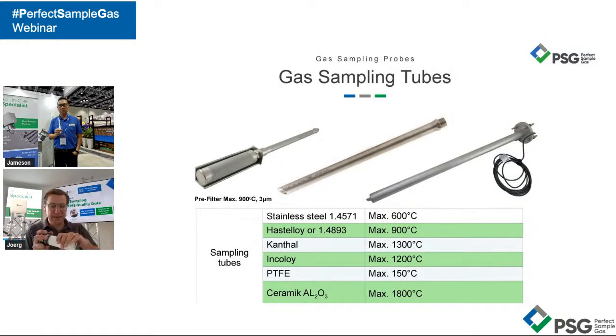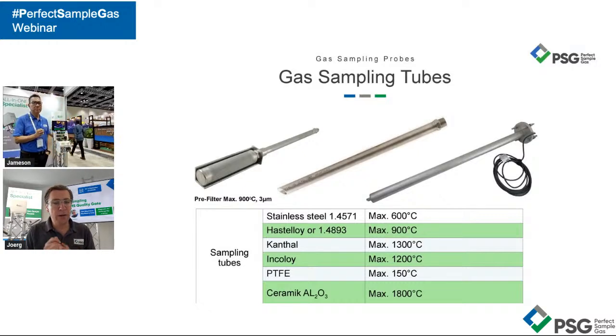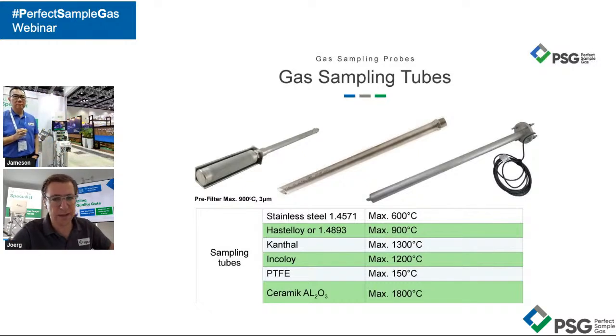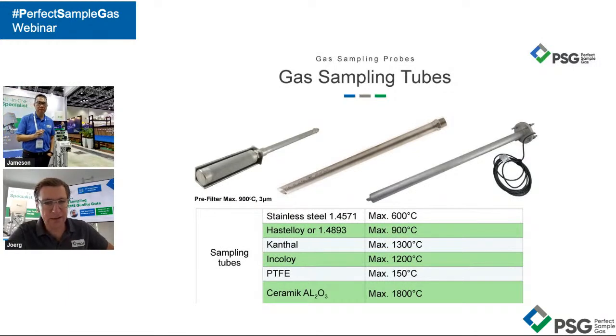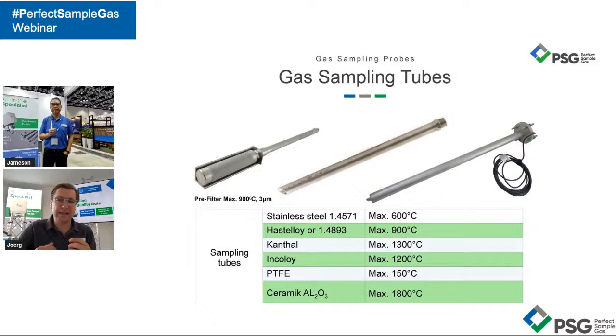Otherwise, the probe or the inside would get clogged very soon. But when we are facing heavy dust applications, which are there not in the emission gas but in the process gas, then we might also recommend choosing a pre-filter. Then obviously, Jameson, this was also something you mentioned, as the gas sampling probe and the probe tube are exposed to the process, it also sometimes has to handle very high temperatures, right?